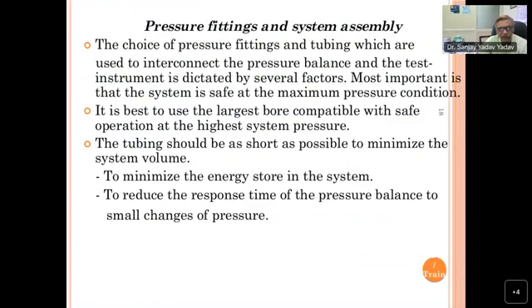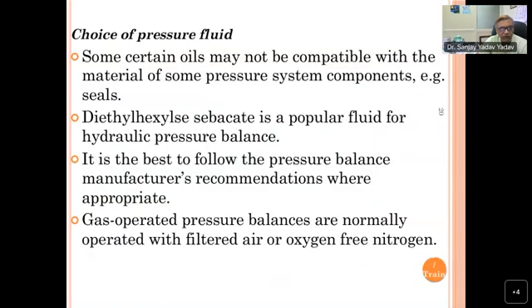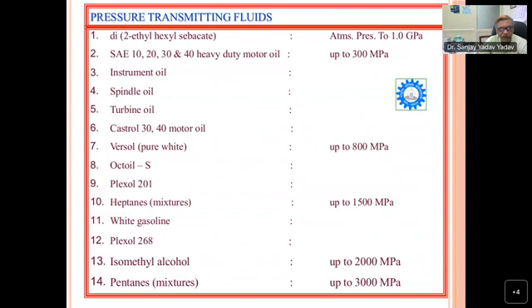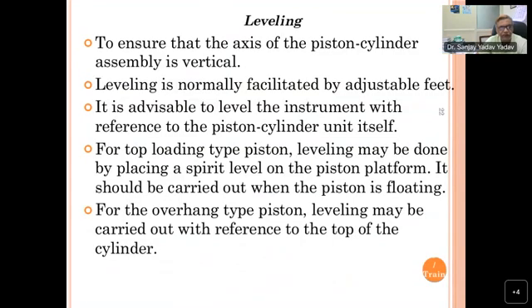Pressure fitting I have covered. This I have covered. Choice of fluid I have covered. This slide I have covered. Leveling. To ensure that the axis of the piston cylinder assembly is vertical, leveling is normally facilitated by adjustable feet. It is advisable to level the instrument with reference to the plane of the piston cylinder unit itself. For a top loading piston, leveling may be done by placing a spirit level. For the overhang type piston, leveling may be carried out at the hanger level.